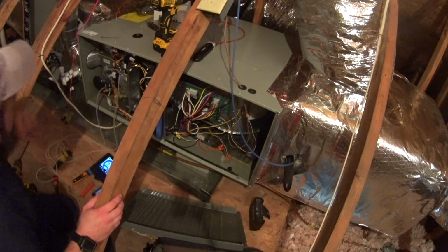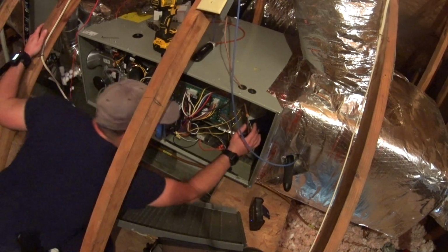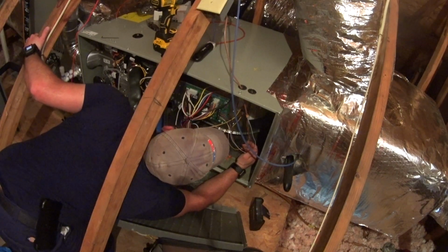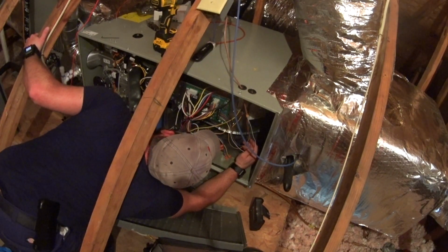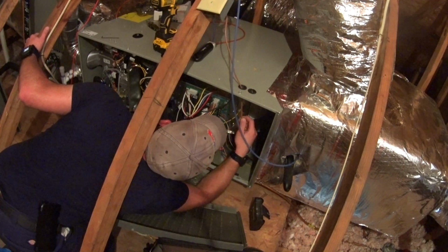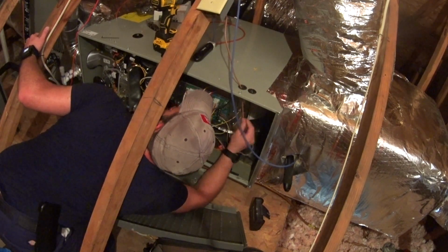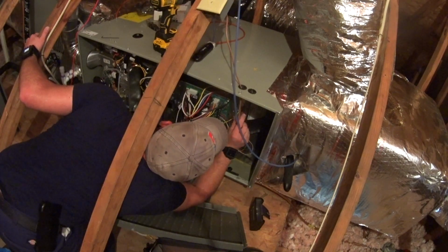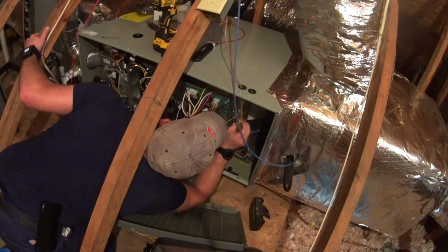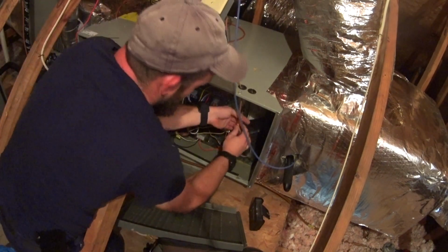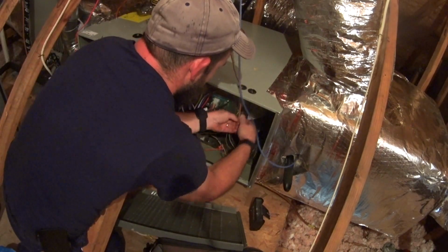We'll go there and let's see what we got for available wires. We've got an orange wire that's available. We could bring it into W2, thinking it should be available over there as well. So we'll go ahead and do that so that the system controls two-stage. The zone board will control two-stage demand or second stage demand.